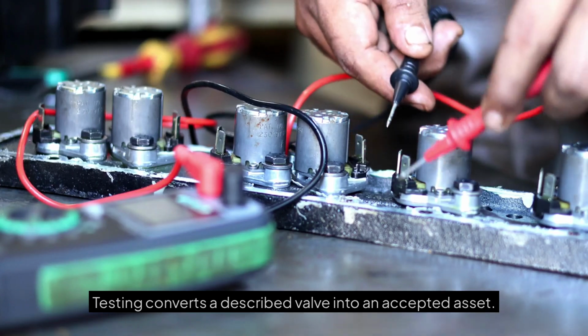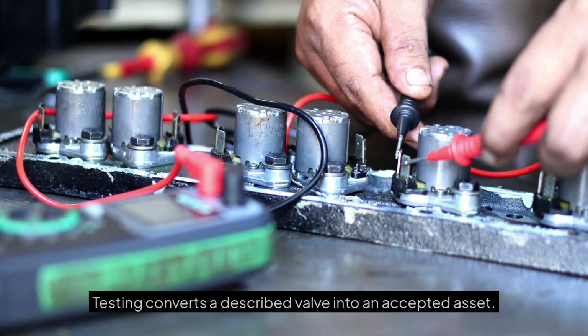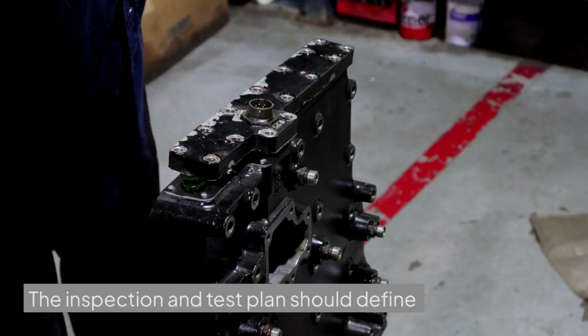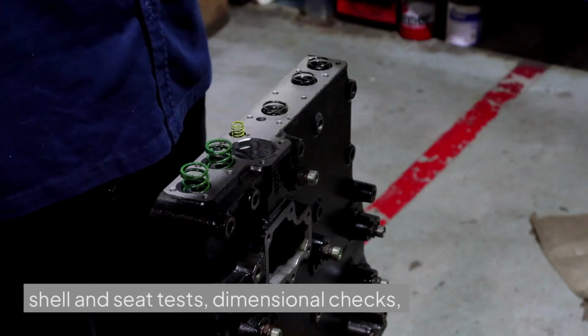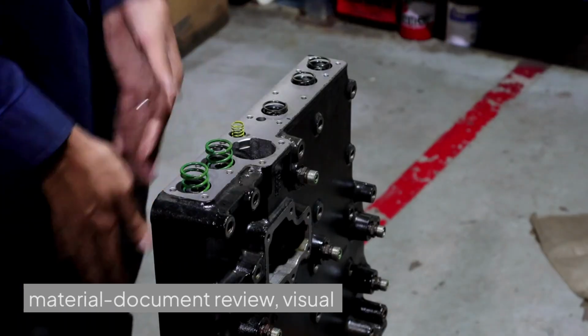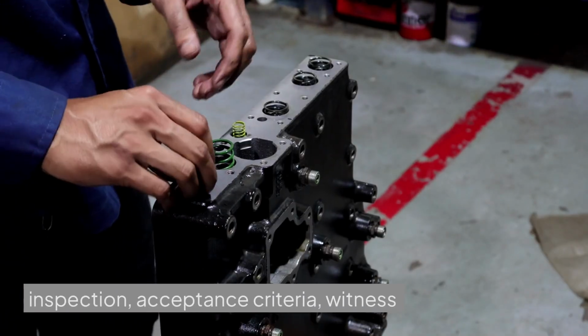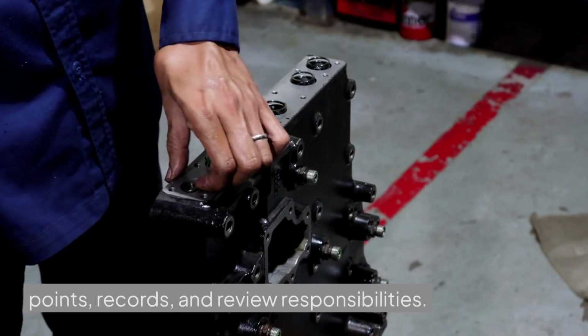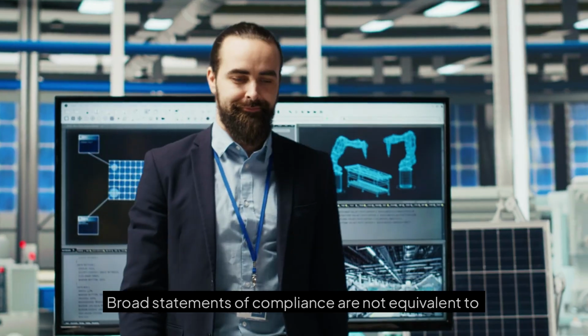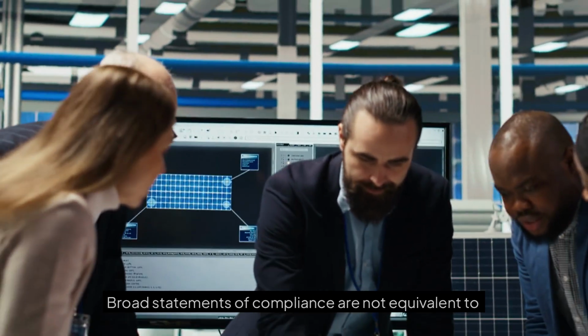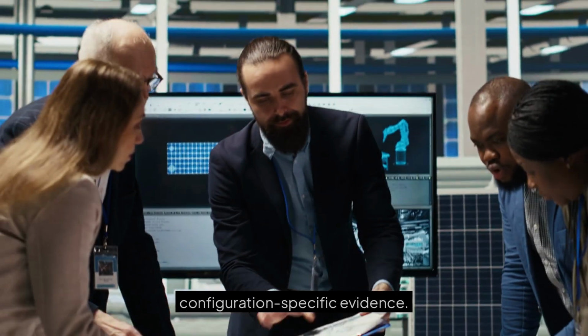Testing converts a described valve into an accepted asset. The inspection and test plan should define shell and seat tests, dimensional checks, material document review, visual inspection, acceptance criteria, witness points, records, and review responsibilities. Broad statements of compliance are not equivalent to configuration-specific evidence.